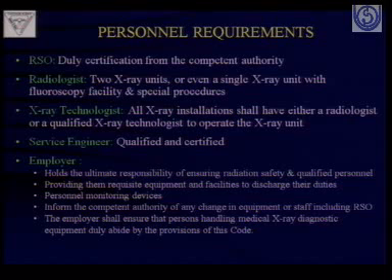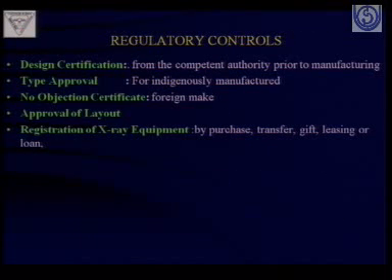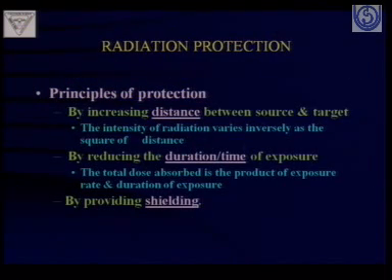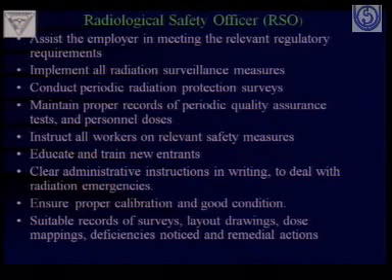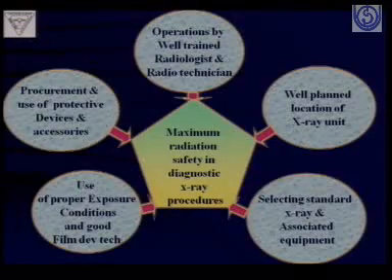X-ray technologists and service engineers have to be qualified, and employers also should get into the detail of what the question asked just now. Various regulatory requirements, as I said: design certification should be there, type should be approved, there should be a no objection certificate, approval of layout should be there, and only registered X-ray equipment should be used. Various RSO duties, as I said, are basically from the safety point of view. The area also needs to be monitored by the RSO.